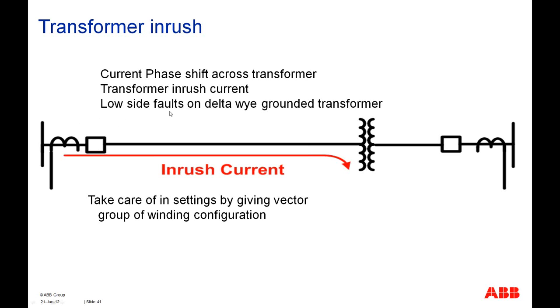And also, we have to take care of the vector group of the transformer, because if, for example, this side of the transformer is connected in Y and grounded, then any fault over here will create a ground fault current, which will be felt by this CT, but not by the remote CT. And then again, we will have an unwanted trip. So we want to avoid this. So we have to take certain measures, like zero sequence current elimination, to avoid this kind of situation.